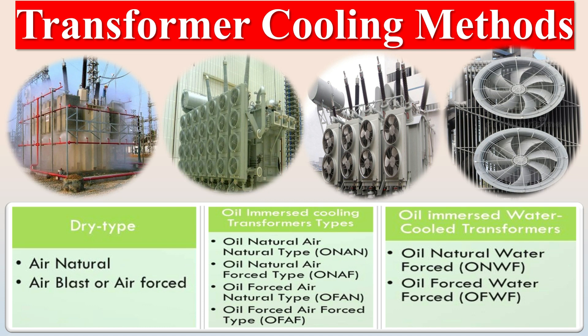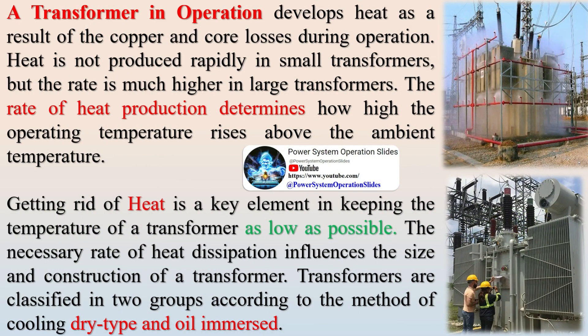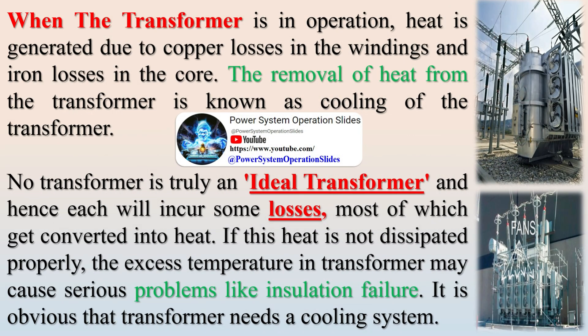A transformer in operation develops heat as a result of copper and core losses during operation. Heat is not produced rapidly in small transformers, but the rate is much higher in large transformers. The rate of heat production determines how high the operating temperature rises above the ambient temperature. Getting rid of heat is a key element in keeping the temperature of a transformer as low as possible, and the necessary rate of heat dissipation influences the size and construction of a transformer.